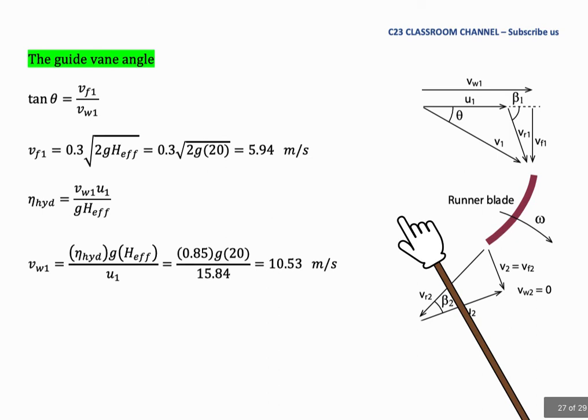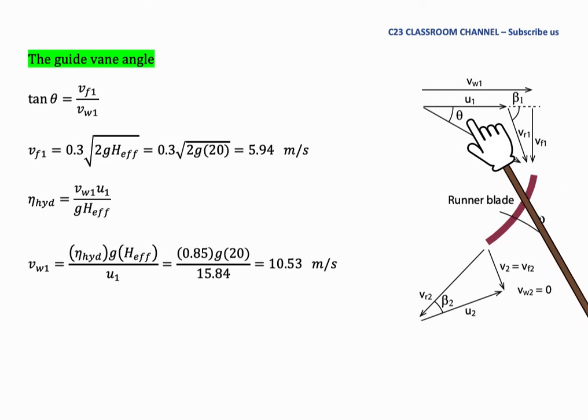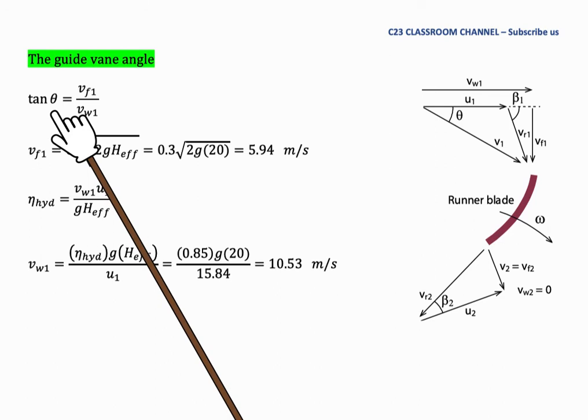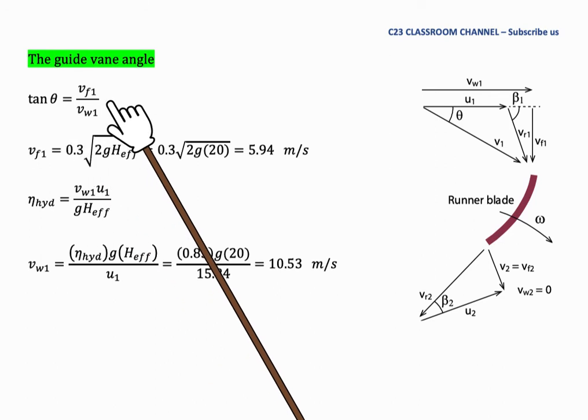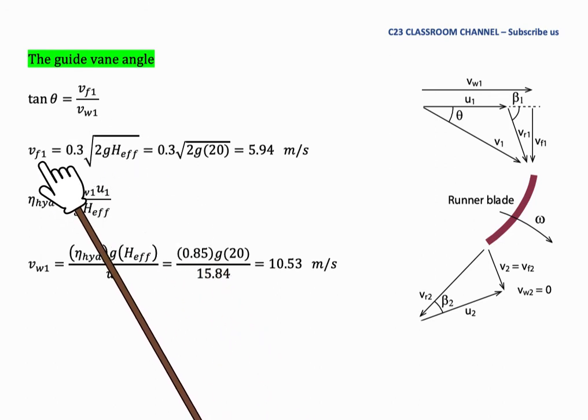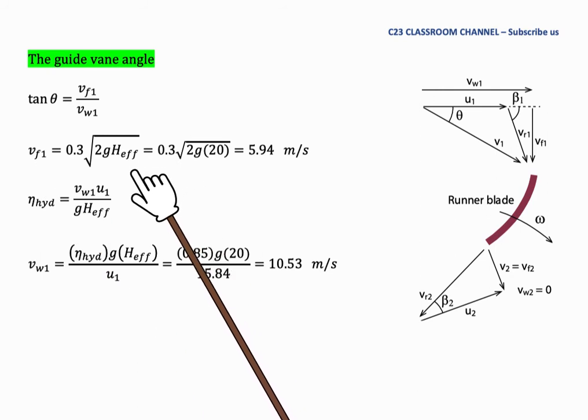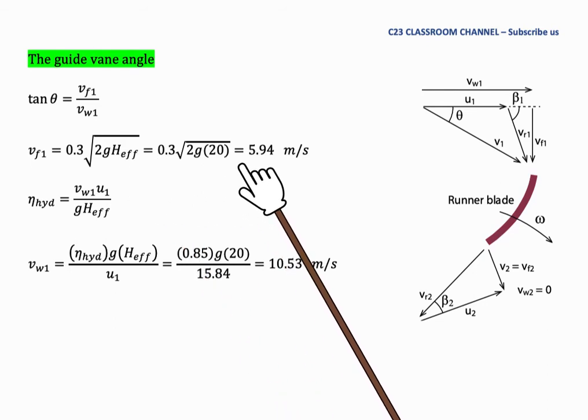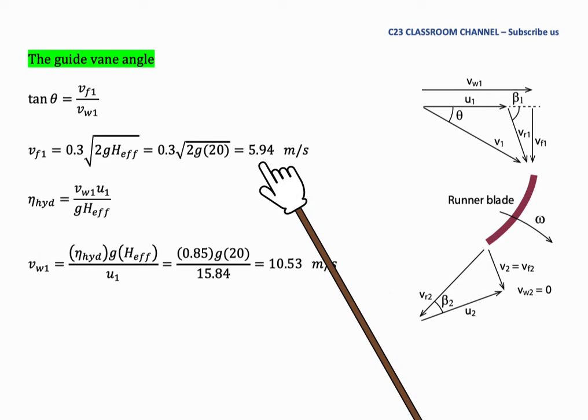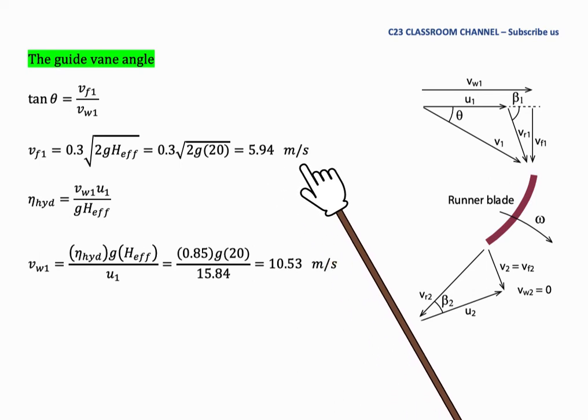Next, we are calculating the guide vane angle. This is the velocity triangle and the guide vane angle is this theta. From the velocity triangle here, we could write tangent theta is equal to VF1 over Vw1. VF1 can be calculated using this equation. We substitute the value of H here with H effective which is 20 meters and we get VF1 is equal to 5.94 meters per second.